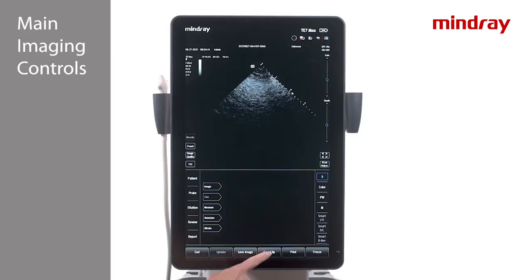To save a clip, press Save Clip. The system is set to either take prospective or retrospective clips. If prospective, the display will show seconds counting down. To print an image to the optional onboard printer, press the print key. The system will need to be plugged in to print. Save an image and print later if not plugged in during the scan. An application specialist can configure the optional onboard printer.